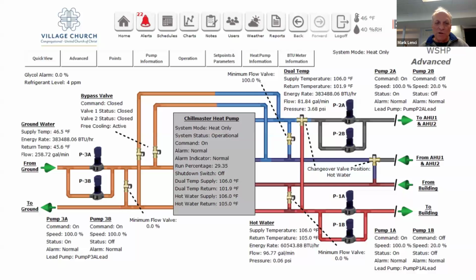The bypass lines, used in air conditioning mode, obviously aren't in use today. We're running at 29.3% capacity of our heat pumps, which puts our hot water out to the radiators at 106 degrees, and to the roof at 106 degrees as well. So this goes up to the roof and back, and this goes out to the radiators and back. That's what it looks like, and those are real numbers.